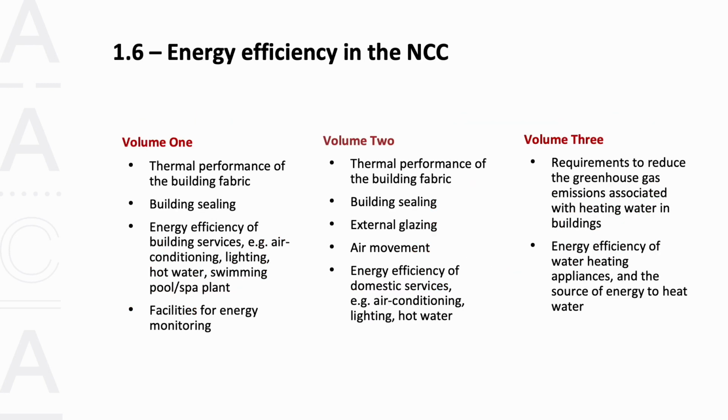Energy efficiency in the NCC. Building energy efficiency is largely assessed by rating likely performance of the building, as designed, against the standard. A building can demonstrate compliance with the majority of the NCC energy efficiency performance requirements by getting a rating against the nominated energy efficiency standard. So some performance requirements require other forms of assessment or evidence. The standards that can be used to rate buildings are different for commercial and non-commercial or domestic buildings. There are also some differences between the standards that are acceptable in different states or territories.